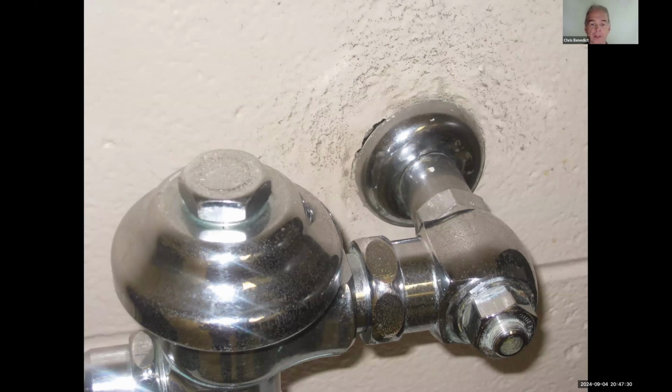It might also leak in at a different time of year, or when fans are different, or maybe when the movie theater is open, it leaks out, and when it's closed, it leaks in. But there's no way to tell from looking, that I know of, if air is ever moving in that hole, because the dust from moving in would be collected somewhere inside the wall. But for a significant portion of the year, depending how often that wall got cleaned, there's a lot of air moving out of that hole.